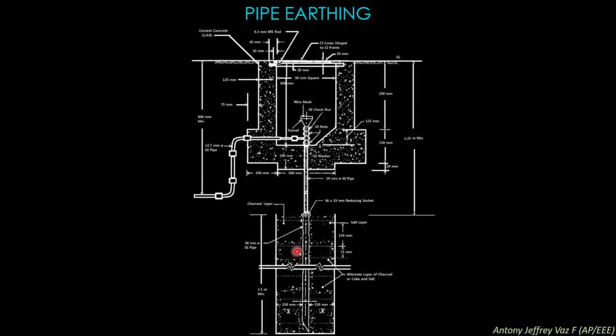There is another type of earthing known as pipe earthing. Here, instead of a metal plate, you are going to insert a huge pipe or metal rod into the ground. Mainly GI pipes are inserted into the ground so that the pipe will not get corroded or damaged due to nature.